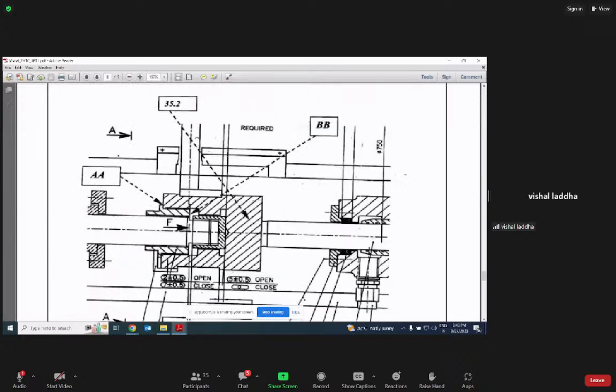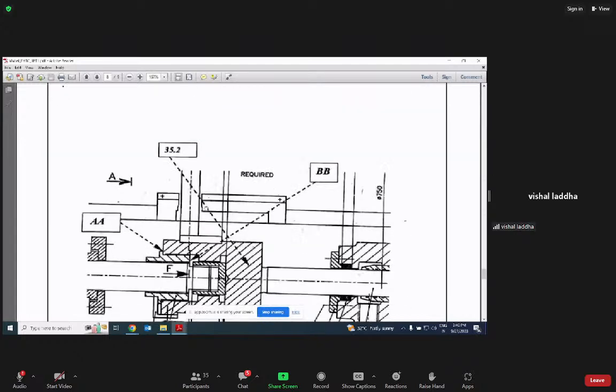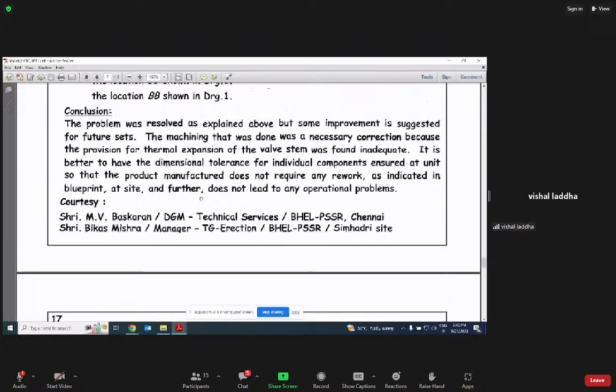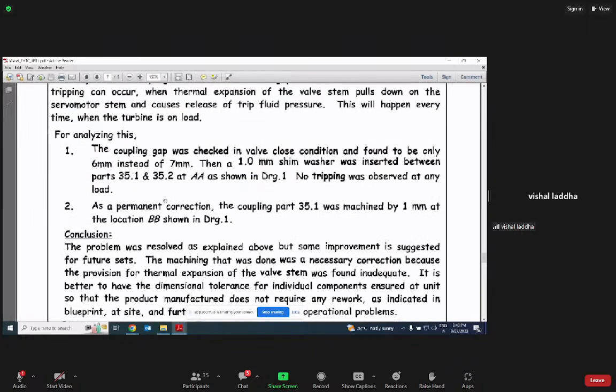Here you just see 35.2, and at the BB position here is shown the machining was done because the difference is only 6 mm, so it should be 7 mm at open and closing condition. So first of all, to run the unit, we just inserted the washer, and after in overhauling, machining was done.